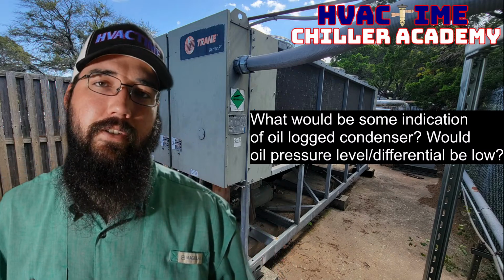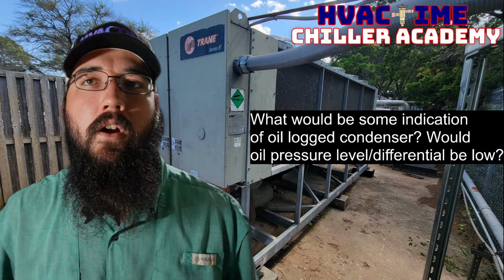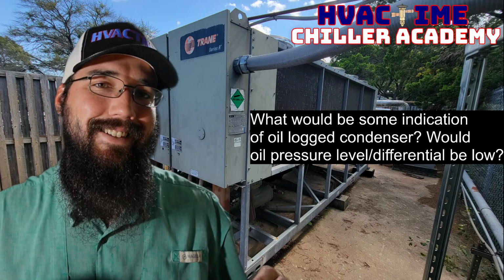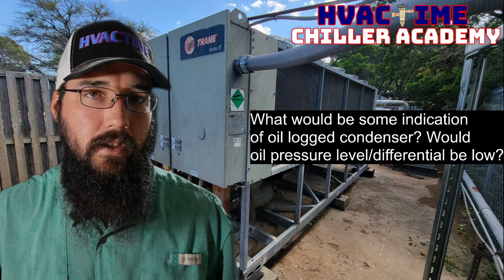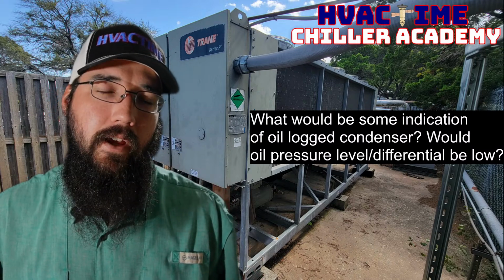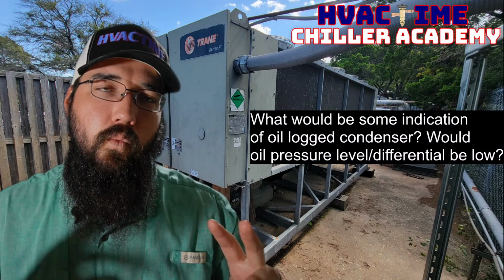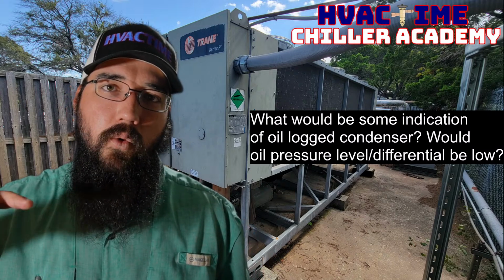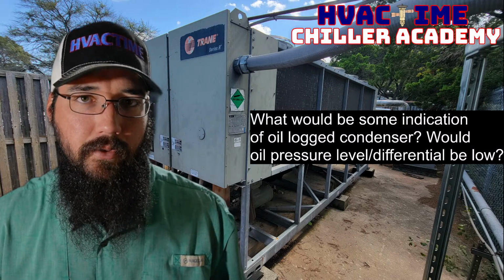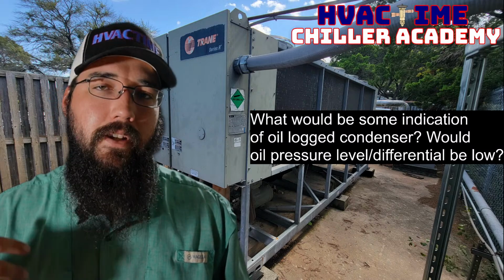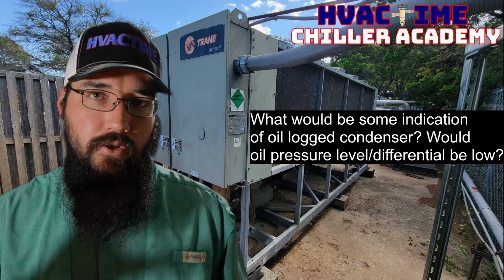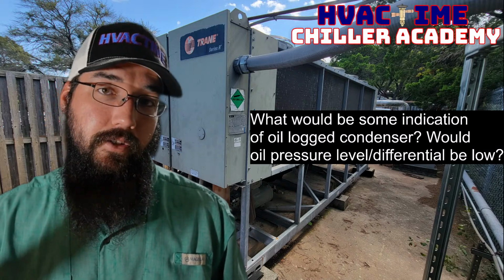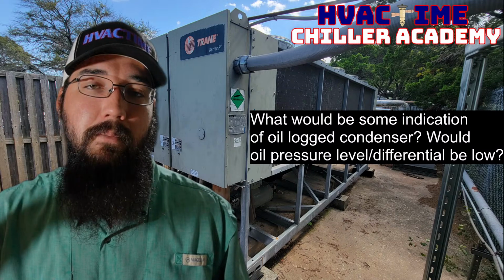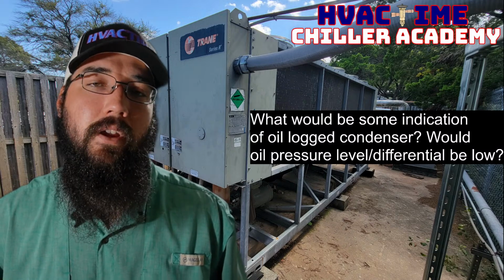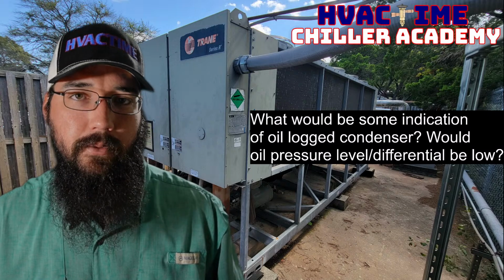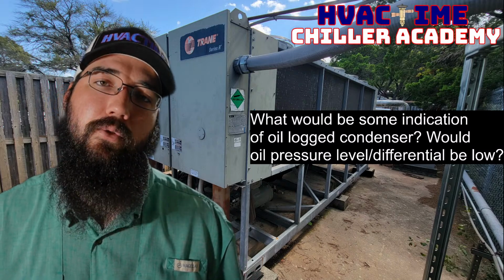The first thing to understand is that the majority of the time our oil is going to log in the evaporator itself, specifically, and there are a few reasons for that. One, the oil is being carried through the discharge line, so it gets carried into the condenser via discharge, which is at the top of the heat exchanger. Then it can gravity drain its way down the heat exchanger into the liquid line, and flow into the evaporator from there.